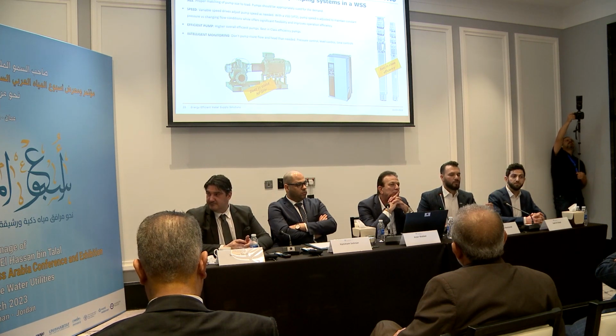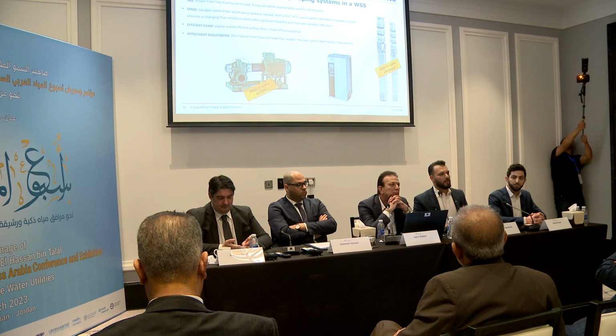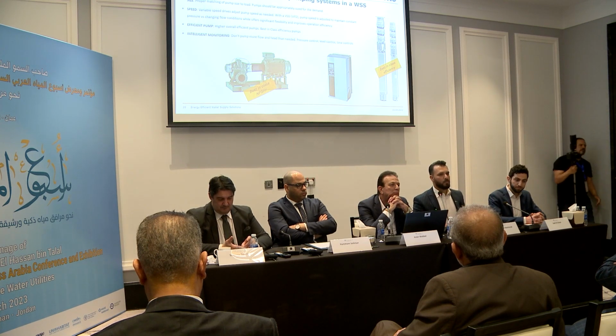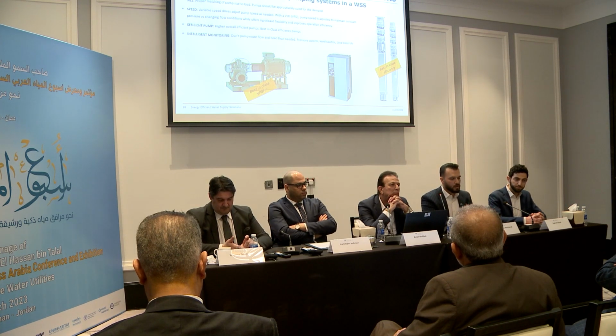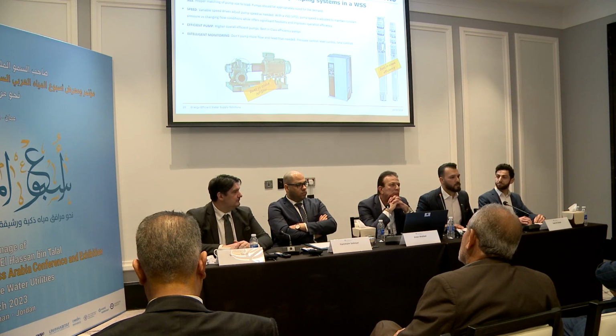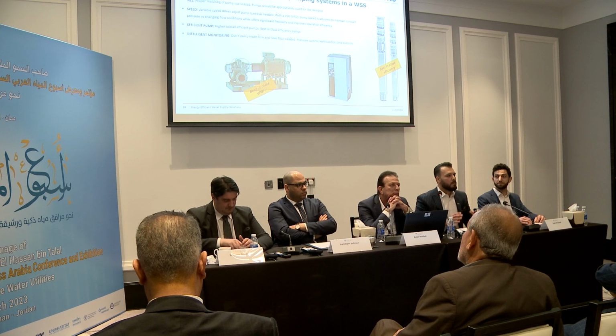Now, most of the pump stations that we are using today just control the pump to have a constant pressure, for example, over a varying flow demand. But we all know if I have a pump station of 5,000 cubic meters per hour at 10 bar, the 10 bar is required when I pump 5,000 cubic meters per hour. But if I pump less flow, for sure I need less pressure.